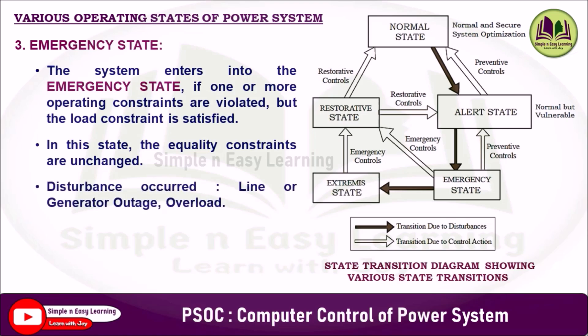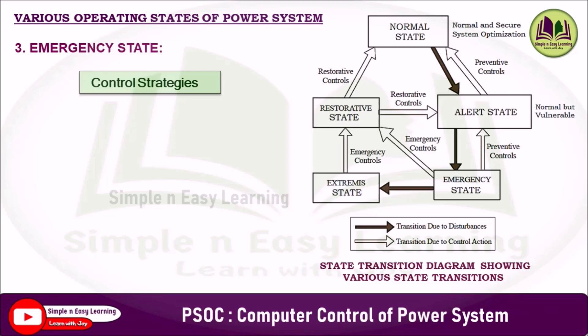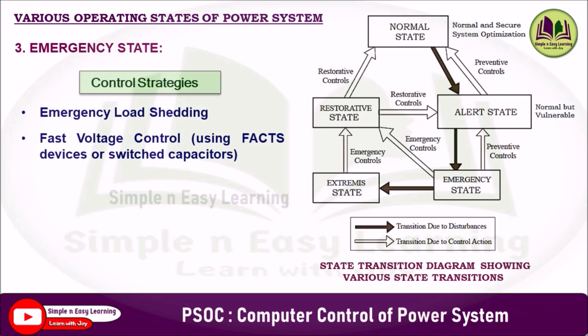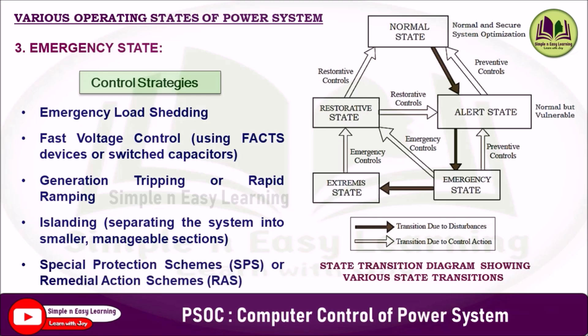In the emergency state, a disturbance has actually occurred — for example, line outage, generator outage, or overload. The system can return to the normal or alert state through corrective actions like disconnection of the faulted section or load shedding. Control strategies include emergency load shedding, fast voltage control using FACTS devices (such as STATCOMs, switched capacitors), generation tripping or rapid ramping, islanding operation (separating the system into smaller manageable sections), and special protection or remedial action schemes.